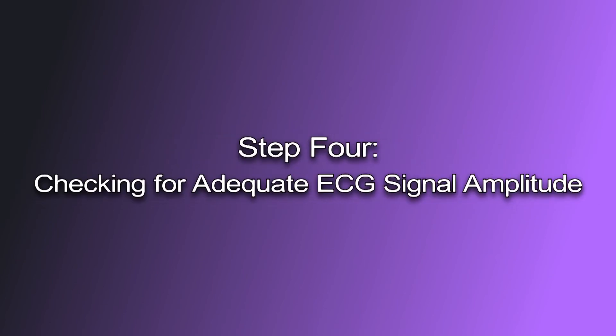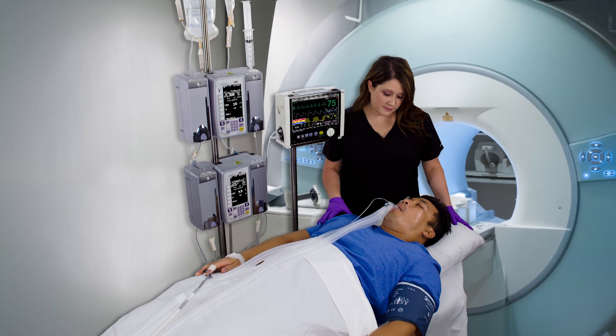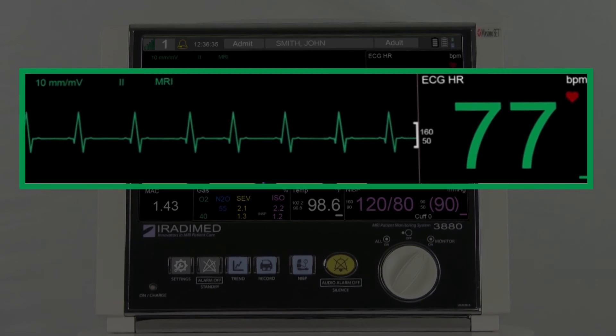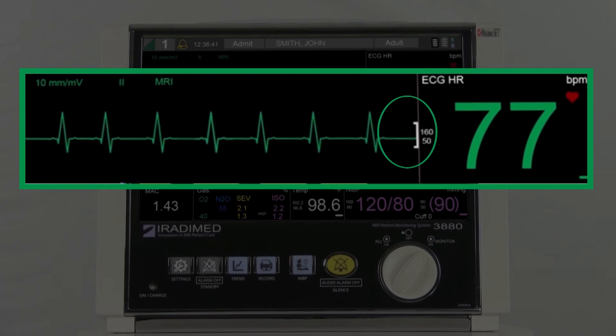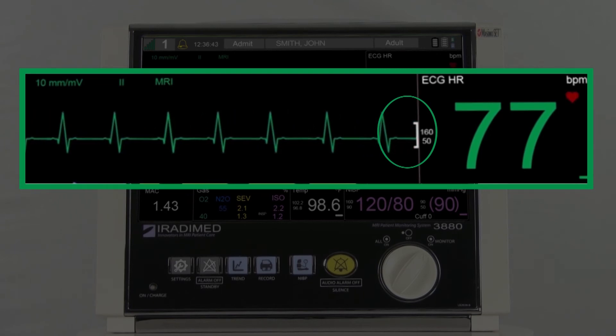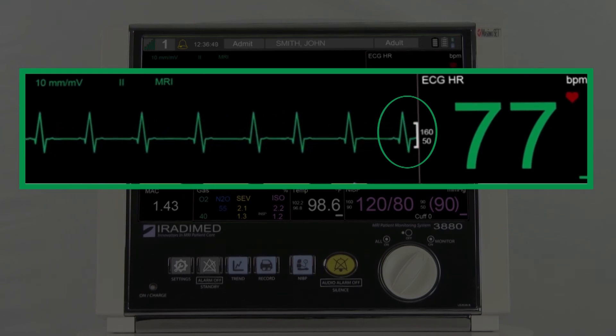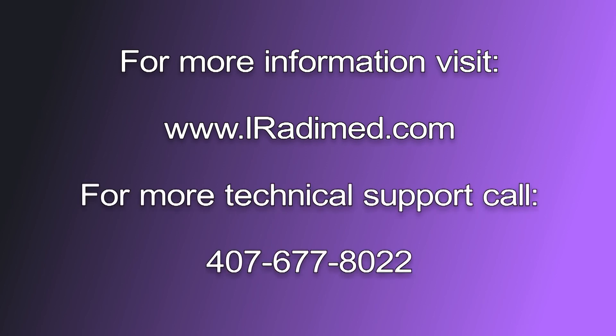Step four: checking for adequate ECG signal amplitude. While the patient is still outside of the MRI bore, observe the ECG signal on the IRadimed 3880 display. The QRS complex should be roughly the same height as the signal quality indicator in the amplitude located on the right side of the waveform. This ensures the minimum signal-to-noise ratio required for the gradient filters to operate. Performing an MRI exam with inadequate ECG signal will amplify gradient artifact and may cause the 3880's heart rate detector to be inaccurate. For more information, visit www.IRadimed.com. For technical support, please call 407-677-8022.